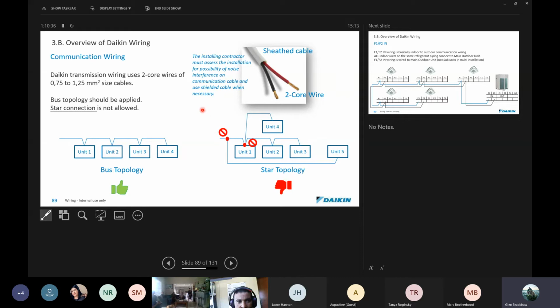Interesting, recently we had guys that had a problem on a site, and after much conversing with the guys, it actually turned up that their problem was a star connection. Okay, so star connections are not allowed. You'll hear guys tell you, oh, we got away with it. Yeah, we've heard guys get away with it, and then a couple of months later, suddenly they pick up a problem, and the system doesn't want to boot up after something happened, and then they've got to go and hunt for their star connection. So sometimes you can, but rather don't be a gambling person. No star connections, follow the daisy chain. Okay, don't allow for any of those star connections. They're going to come back and bite you.